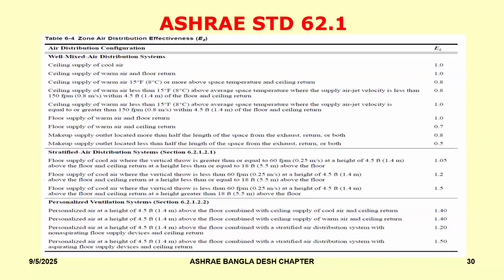So typically, instead of 500, you probably end up putting around 585 CFM or so. So what it means is, if your air distribution system is not effective, then you will need to bring in more outdoor air. There is a penalty you pay, especially in places like, say, Dhaka or Bombay or Madras, where your outside enthalpy is very high. When you're taking outdoor air, conditioning it, and then bringing it in, if you have to bring in more air, obviously the amount of energy you will spend is going to be greater. And therefore, you want to make sure that your room air distribution effectiveness is 1 or higher than 1.